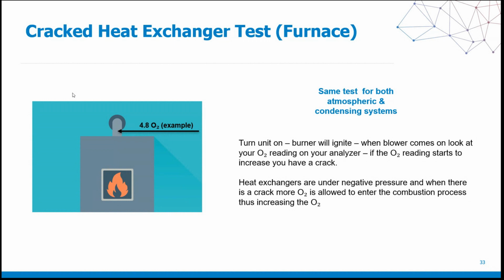But again, the analyzer can prove to you that you have it. So what you have now is both a newer technician and an experienced technician that can prove and show to a homeowner or business owner, here is your crack in your heat exchanger, and these are the results of the analysis, and this is what it's showing you, and explain it to them. It ups everybody's game, and it increases everybody's credibility. And at the end of the day, what that increase in credibility does is it reduces liability significantly, because you've properly tested that appliance and have properly come up with what the numbers are and what the plan of action is going to be.